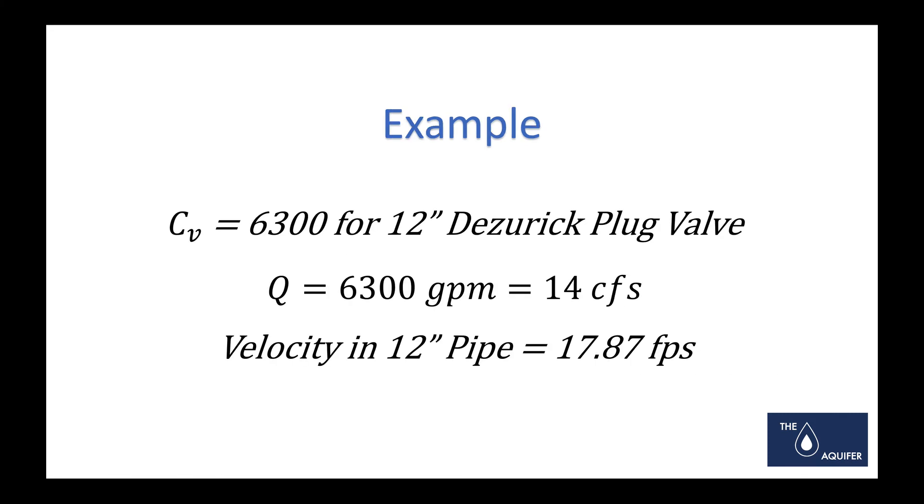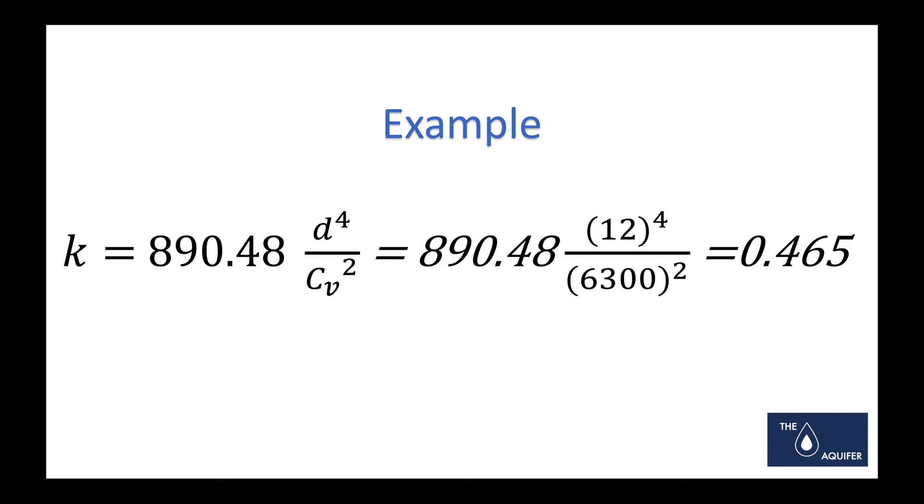I'll provide you with a little bit of an example here. Let's say we're working on a 12-inch Dezurik plug valve and they give us a Cv of 6300. Well, the 6300 gallons per minute equates to 14 cfs in a 12-inch pipe, and the velocity in that pipe would be 17.87 feet per second. As you can tell, these are pretty high for a normal pressure pipe system that we might do in a municipal water/sewer application.